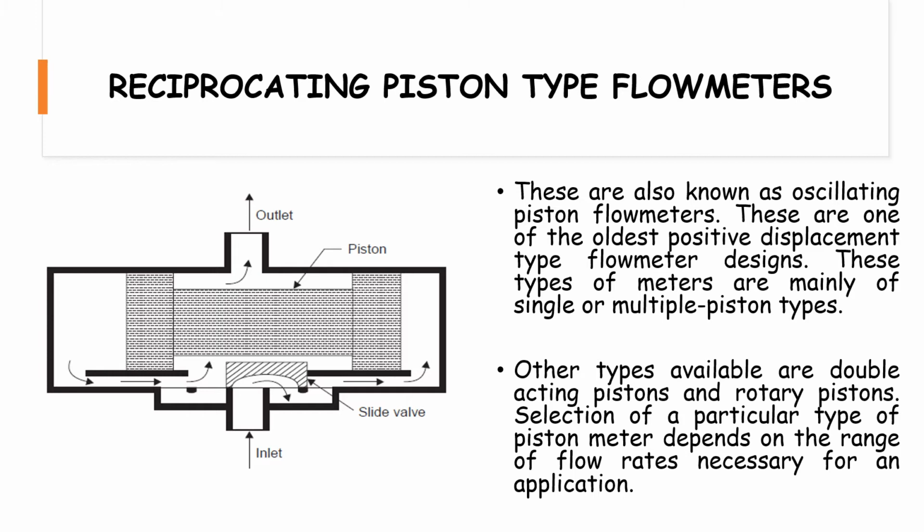Now here a number of piston operations on a center crank are generally incorporated in this type of flow meter. For a low flow, the differential pressure is small, for which larger diameter pistons and small piston strokes are chosen with a minimum of friction. Accuracy of this flow meter is within 0.5%. Now, although piston meters are smaller in size and also considered apt for handling only low flows of viscous liquids, yet they are proficient enough to deal with an extensive range of liquids.